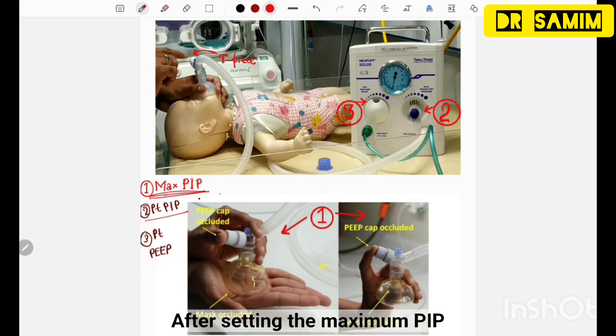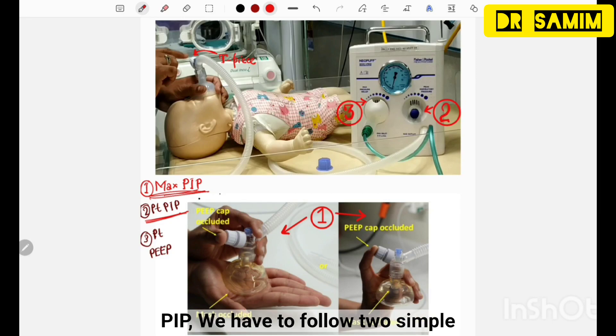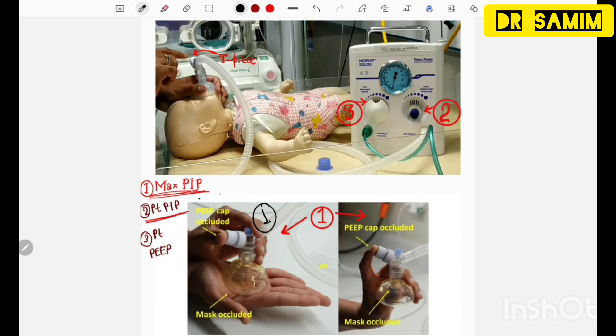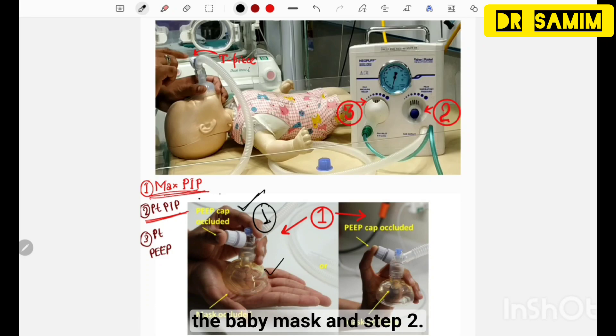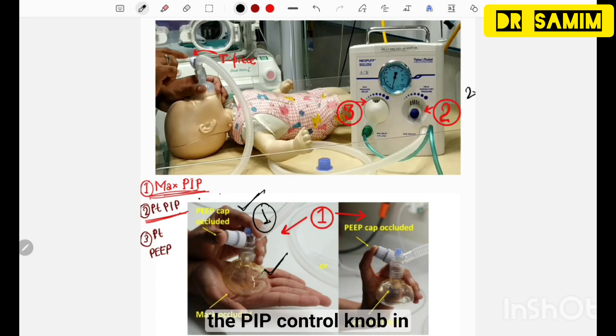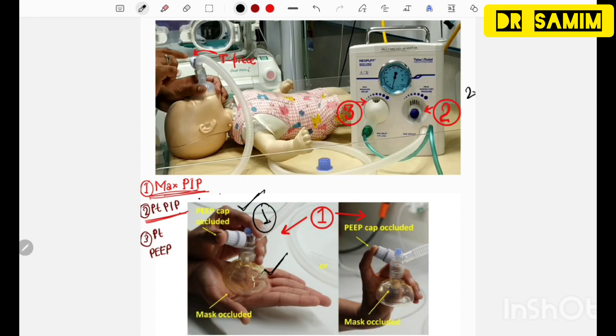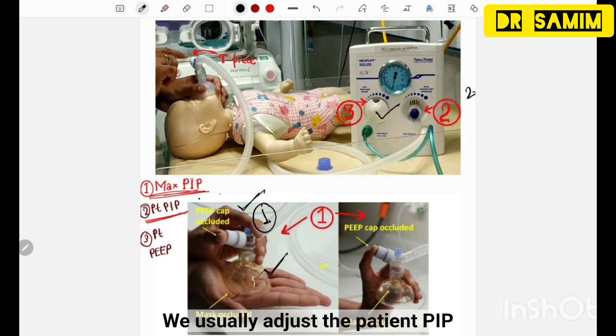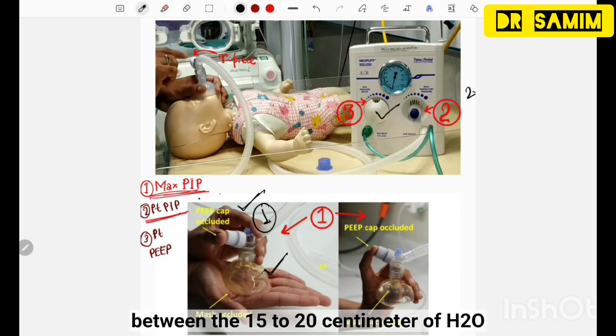After setting the maximum PIP, we now set the patient PIP. To set patient PIP, follow two simple steps. Step 1: occlude the circuit by occluding the PEEP cap and the baby mask. Step 2: rotate the PIP control knob in the anticlockwise direction to adjust the desired PIP. Do not touch the pressure release knob. We usually adjust the patient PIP at 15 cmH2O, or between 15 to 20 cmH2O.